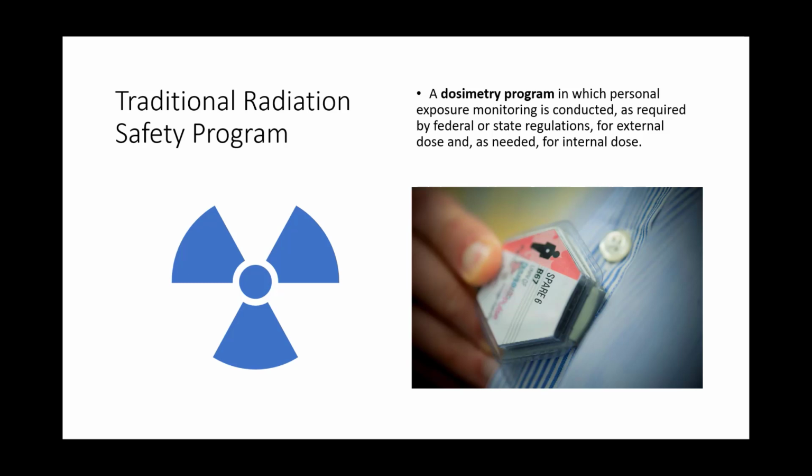It is sensible only to monitor those people that require monitoring, and not monitor everyone who comes in contact with radiation, period. You want to monitor occupational workers. People that occasionally come in contact with radiation, such as a transporter or a nurse in the surgery department, may or may not need a radiation monitoring device. It depends on the time and the dose that they are being exposed to.